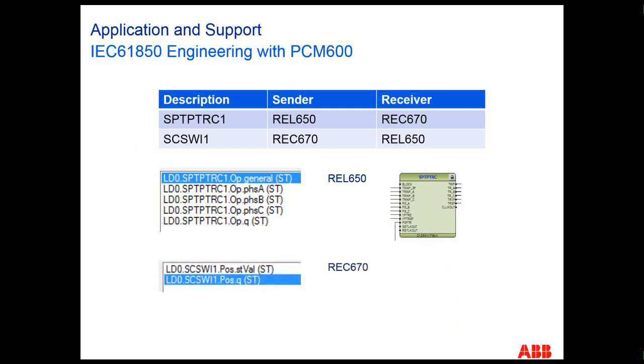In the case of the circuit breaker position, this is going to come from the SCSWI1 POS STVAL, and we also have to include the quality. This will be a second GOOSE message. Each relay is going to publish a GOOSE message — in the case of the REL650, it is going to contain the trip signal, and in the case of the REC670, the circuit breaker position.